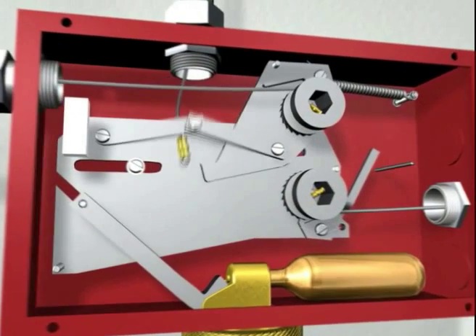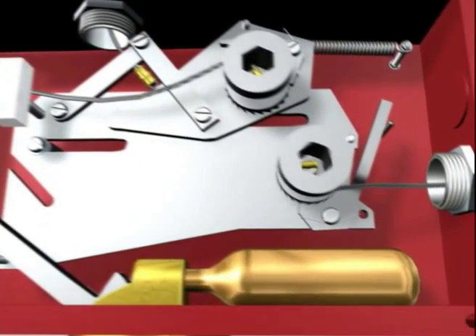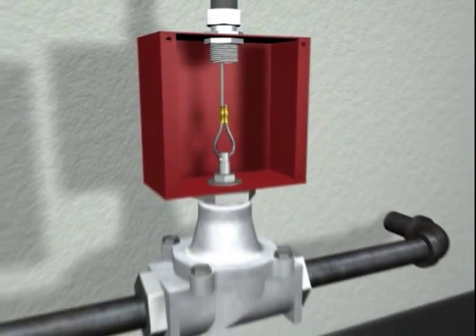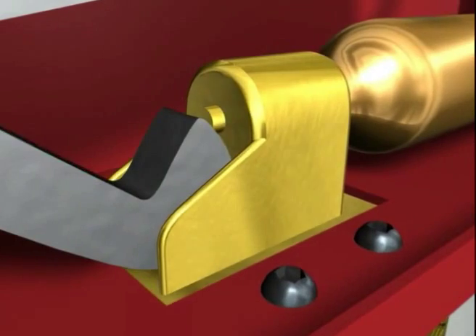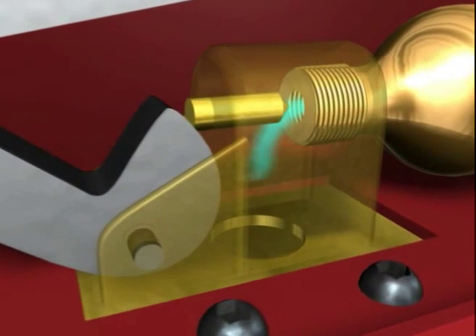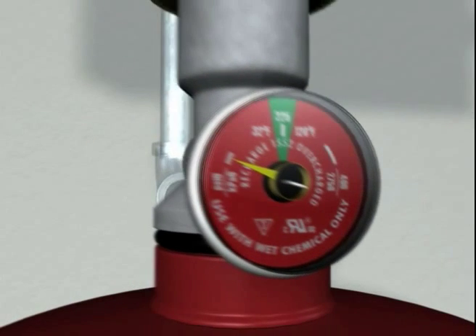The wire triggers the gas valve to shut off. Simultaneously, the system is actuated as a pin punctures the small CO2 cartridge within the mechanical control head. The cartridge pressure opens the agent tank valve, allowing the wet chemical agent to flow freely throughout the piping network.